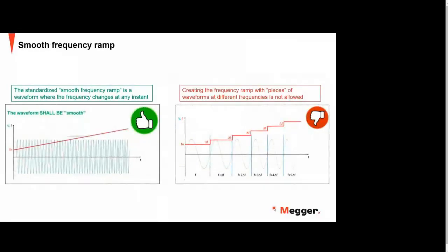So when you make a ramp, and that's what we recommend to use when testing frequency protection, use the ramp function in the relay test sets. This ramp should be smooth, and that means that the frequency should be changed in microseconds when you're ramping. It should not be changed in pieces, like in milliseconds, for example every cycle or every half cycle, like a staircase. That's not allowed according to the new frequency standard. So this is one important thing when you simulate a frequency change from the relay test sets. It should be very smooth.